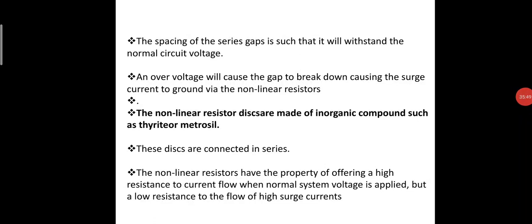The non-linear resistors have the property of offering a high resistance to current flow when normal system voltage is applied, but a low resistance to the flow of high surge currents.